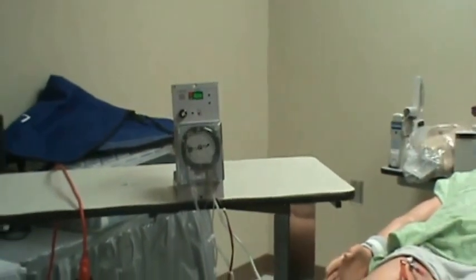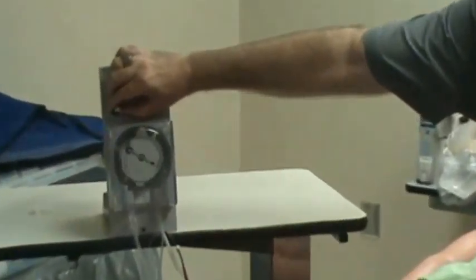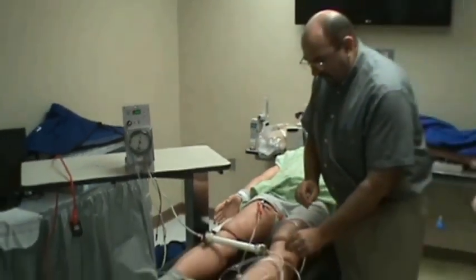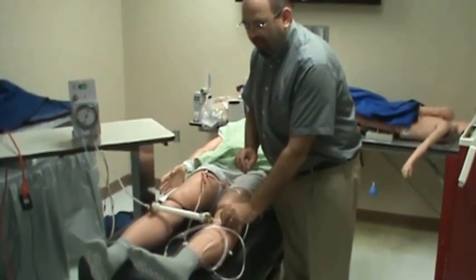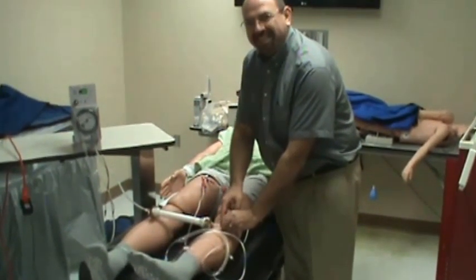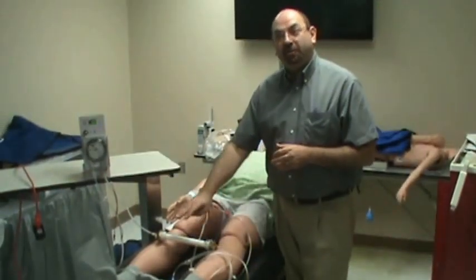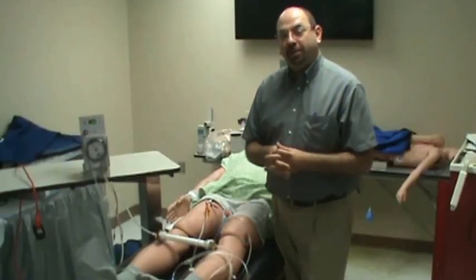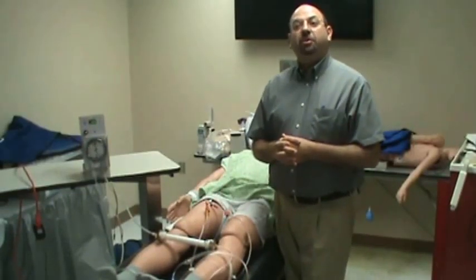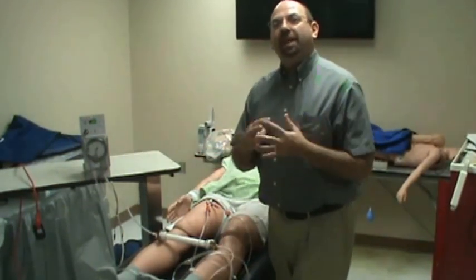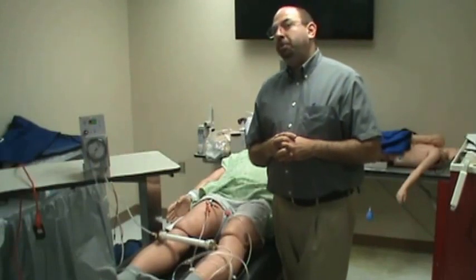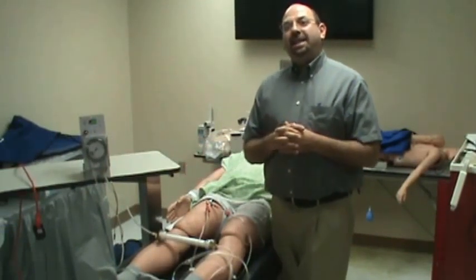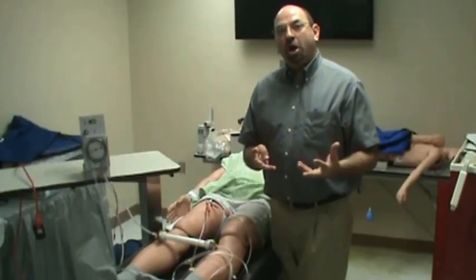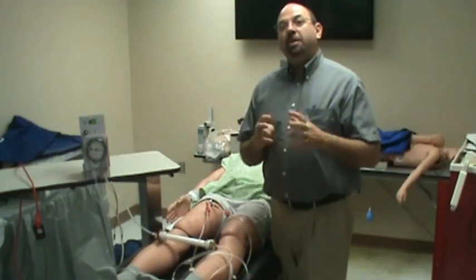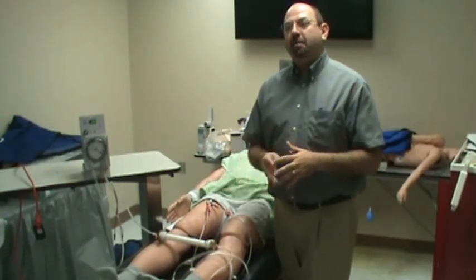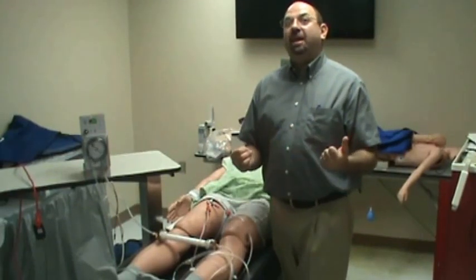You notice the pump speed has increased. Or you just get a hemostat and bend this catheter a little bit, and once you increase the resistance in that catheter, the pressure within the hollow fibers of the hemofilter increases, and that increases ultrafiltration. So you may go up to 1200 or even 1500 cc's an hour. In that situation, you would immediately relieve pulmonary edema. Keep in mind that it's all about pulmonary edema. It's not about the total body edema initially. If the patient is having hypoxia, is hard to oxygenate, or becomes intubated on the ventilator, the most important thing is to clear their pulmonary edema. And they may not tolerate more than 5 liters of negative fluid balance.